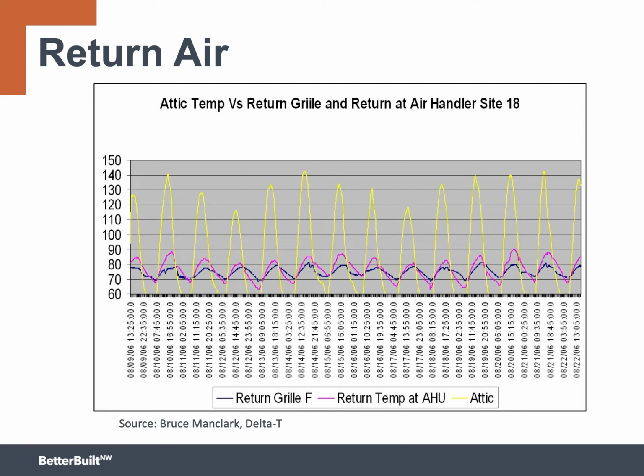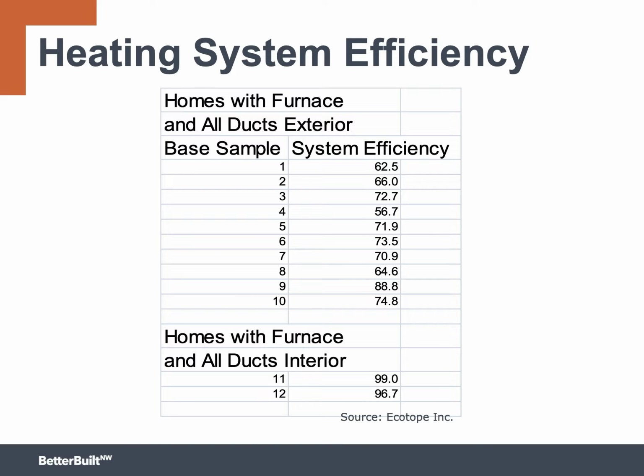In case there's any doubt that attic temperature affects the air inside ducts, this chart shows that high attic temperature corresponds perfectly with the high return air temperatures. These temperature measurements were taken in 3 locations: the attic, the return grill, essentially room air temperature, and the return air stream at the air handler. If you could zoom in on this graph, you would see that there's about a 10% increase in the air temperature at the air handler. That's the heat that's being picked up as the air goes through the return duct in the attic on a hot day. And the same principle applies in winter, except that here in the Pacific Northwest, the ducts are losing heat to the cold attic, and this occurs for many more hours during the year than losses during the cooling season.